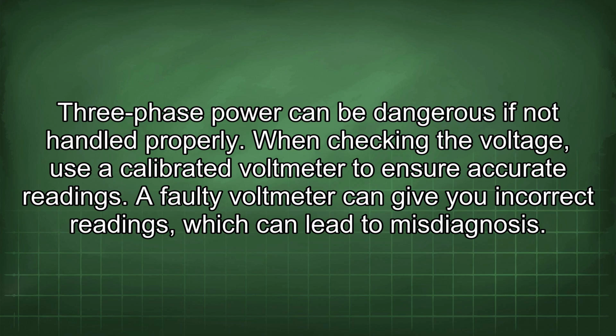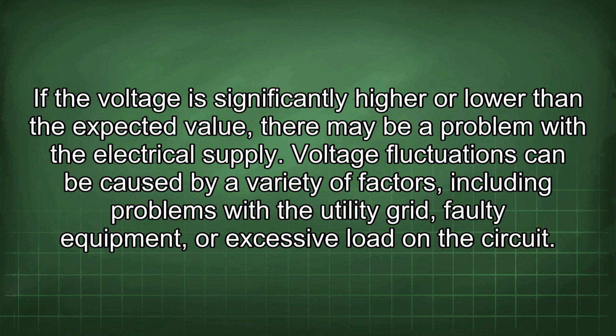When checking the voltage, use a calibrated voltmeter to ensure accurate readings. A faulty voltmeter can give you incorrect readings, which can lead to misdiagnosis. If the voltage is significantly higher or lower than the expected value, there may be a problem with the electrical supply. Voltage fluctuations can be caused by a variety of factors, including problems with the utility grid, faulty equipment, or excessive load on the circuit.